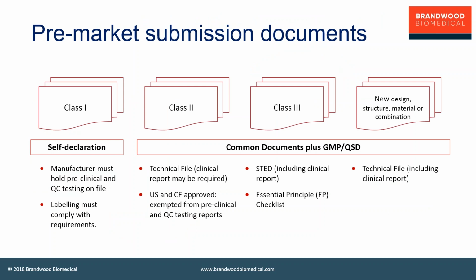The pre-market submission documents are like this. This is set out for class 1, class 2, class 3, and devices which are completely new in design, structure, or material, or a combination. So for class 1 devices, it's a self-declaration. You must hold the preclinical and quality control testing on file, and your labeling must comply with requirements. For class 2 devices and class 3, you need the common document set that we referred to earlier in the presentation, plus the QSD certificate. For class 2 devices, you will need to have a technical file, and the clinical evaluation may be required to be submitted. Sometimes the agency will specifically request that.